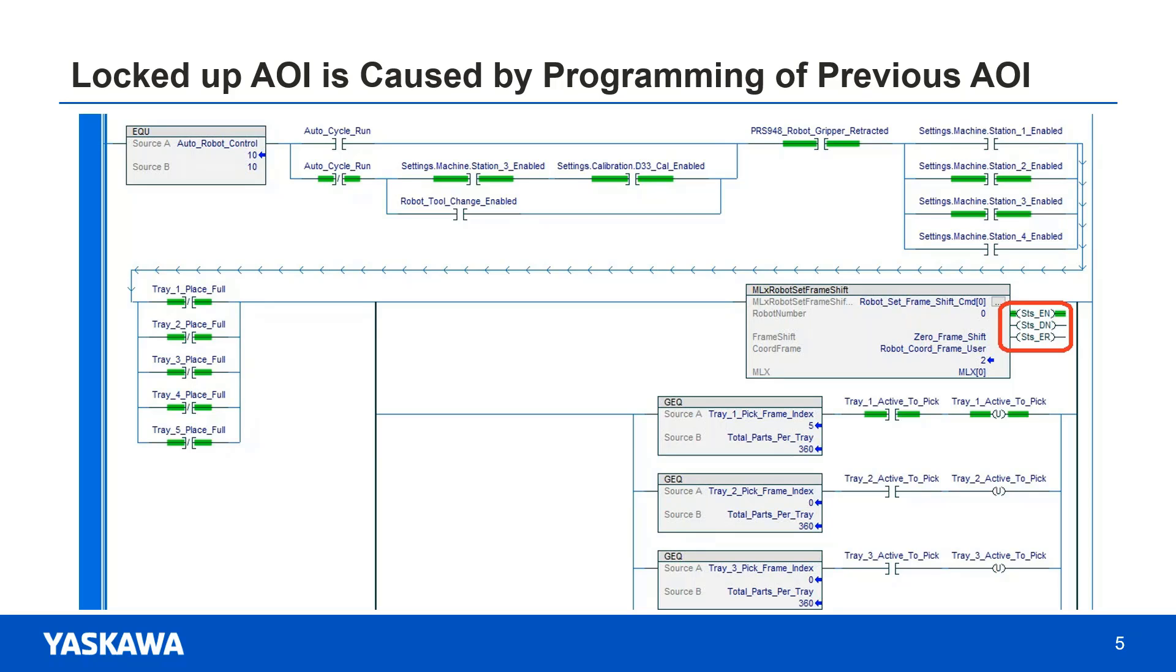Almost every time this happens, it's not a problem with the current AOI. It's because the previous AOI was not programmed properly. More than likely, the previous AOI had its rung disabled before it was done.